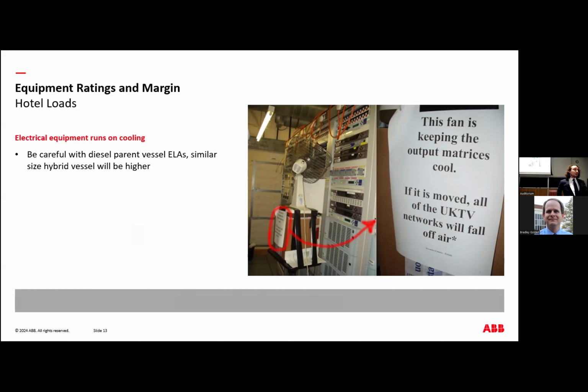And in general, if you're using a parent vessel, which is very risky, and there's a great article from Professor Collette at University of Michigan online about why parent vessel design is risky. But if you're doing it specifically, the electric load analysis is extremely risky to use as a parent input, because the hybrid or all electric vessel is going to have a higher electrical load. We've got cooling pumps for all these systems, often 2 circuits, cooling fans for pretty much everything. There's anti-condensation heaters in most electrical equipment, transformers, propulsion motors, the multi-drive lineups that we provide to prevent condensation when the equipment cools down.